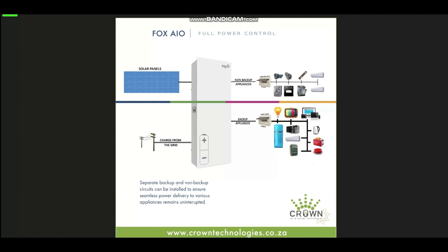The last thing I'd like to mention is the difference between an off-grid inverter and an on-grid inverter. For me, the biggest frustration with an off-grid inverter, which is kind of your cheap and cheerful stuff that you can buy over the counter at Ellies or AC/DC, is the fact that it only has a single AC output. Now, the biggest problem for me, as having owned an off-grid inverter, is if your battery is full and your essentials are not consuming the total solar production, your surplus is just completely wasted.